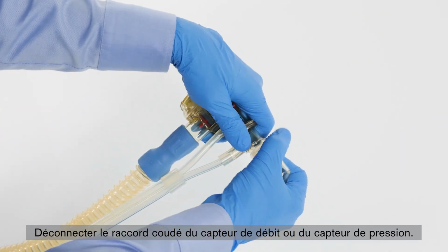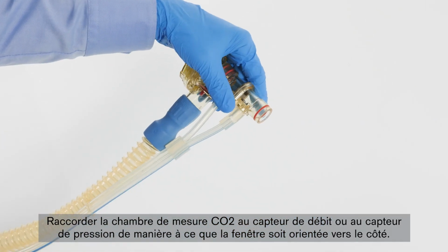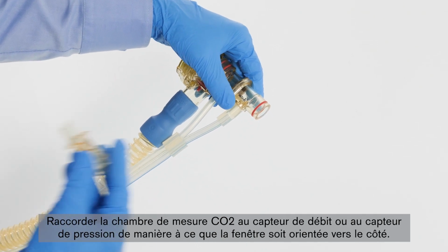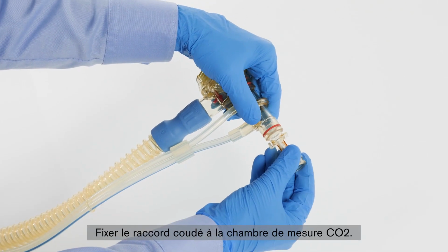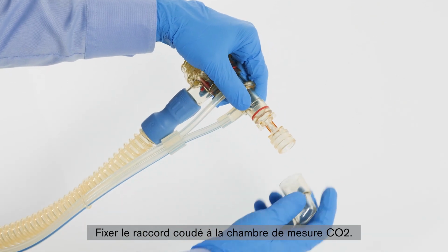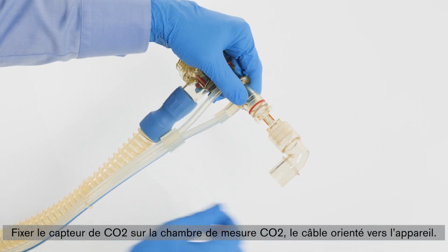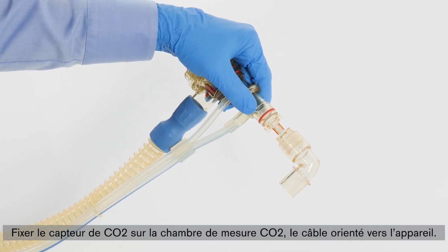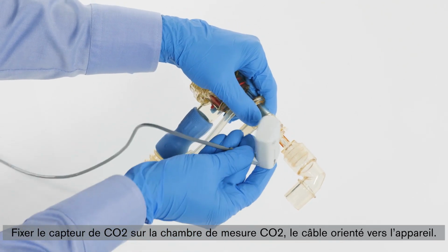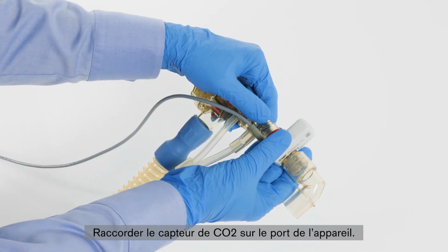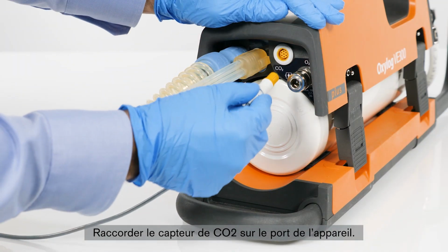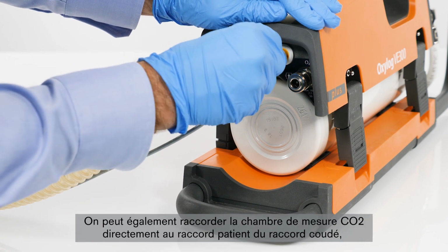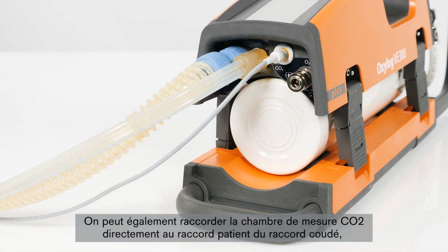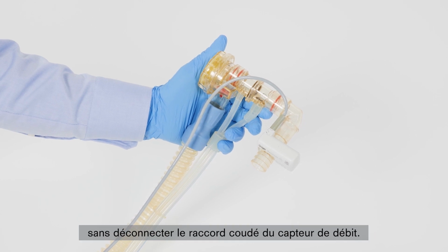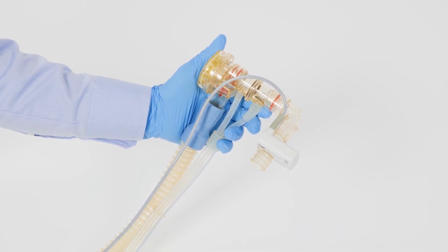Disconnect the elbow from the flow sensor or pressure sensor. Connect the CO2 cuvette to the flow sensor or pressure sensor so that the windows point to the side. Attach the elbow to the CO2 cuvette. Push the CO2 sensor onto the CO2 cuvette with the cable toward the device. Connect the CO2 sensor to the port on the device. Alternatively, connect the CO2 cuvette directly to the patient port of the elbow without disconnecting the elbow from the flow sensor.